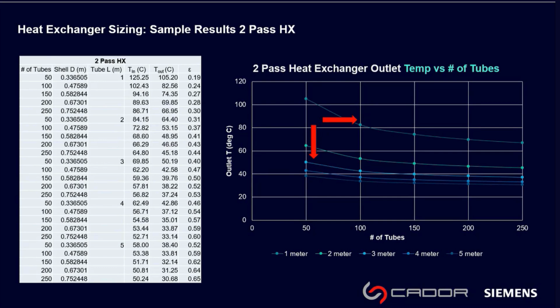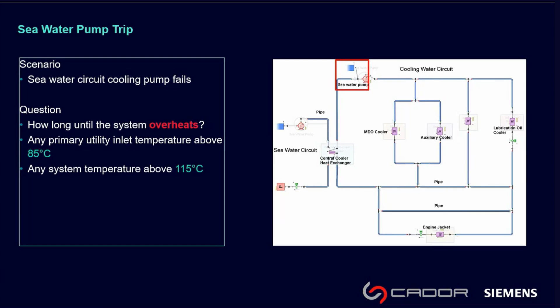I mean, obviously you can predict failures. There are a number of ways you can do that. Generally people tend to ask, if we had pumps and one or two of them failed, what would happen? How long would it take for the system to overheat? Any primary utility inlet temperature above a certain temperature, for example, in this case is written as 85. You may want to see when it would go beyond 115 or 120, or whatever the temperature range is that you may want to avoid. So those things can be modeled in Flomaster as well.